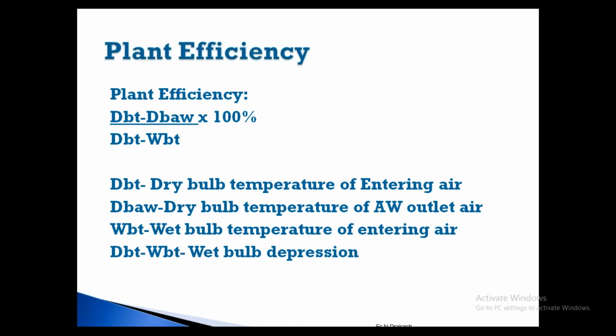Because of the poor spray, proper mixing is not happening, and your distribution is not happening. Some plates are open, some eliminators are not proper, it is all blocked. So there are so many reasons for the inefficiency of the plant. Even for the water spray, this many liters of water is to be sprayed for this much air, so that mixing has to be done properly.